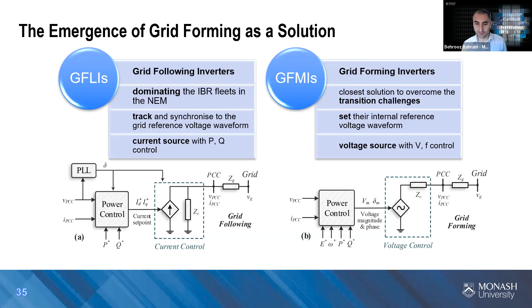Grid forming inverters, on the other hand, do not need a PLL to get synchronized to the grid. They are power synchronized, meaning they can instantaneously sense any changes in the network, which helps them work in very weak parts of the network for two reasons: they are not dependent on an external voltage source, since PLLs are typically the source of instability in weak networks, and they themselves form the voltage at the point of connection. So they've got that advantage of connecting to very weak networks.